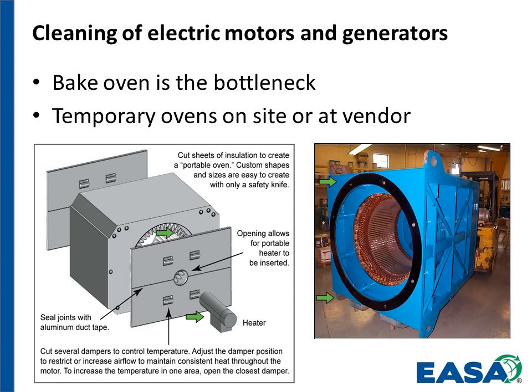So pretty simple process. If you're familiar with wood stoves, we're just using openings cut into this aluminum board so that we can control the rate at which the air flows through and control the temperatures. Larger machines like these, in most cases, particularly with the petrochemical industry, are fitted with winding RTDs. So we can tell when the winding is up to temperature, so that's pretty helpful.